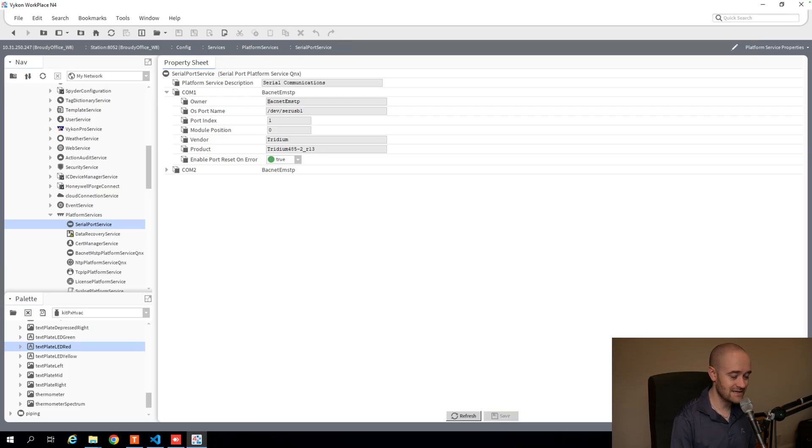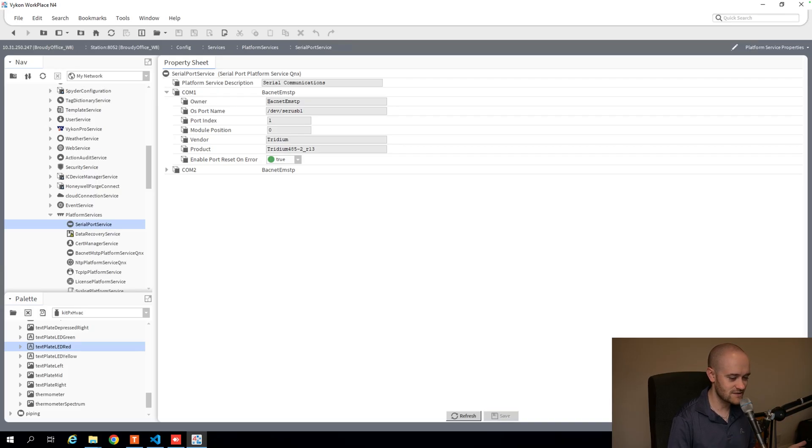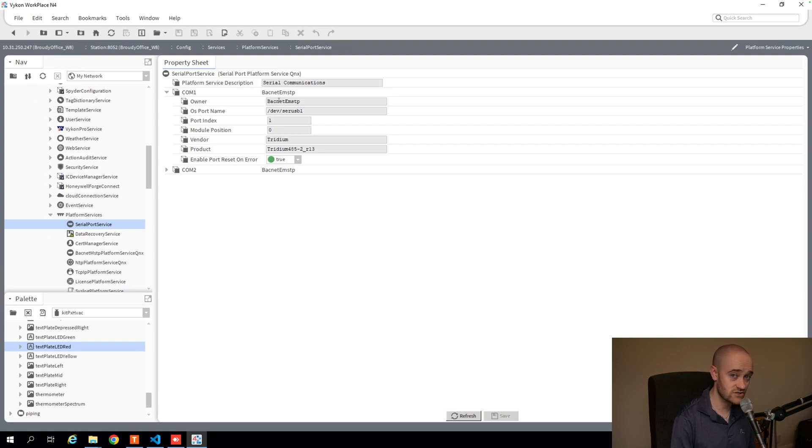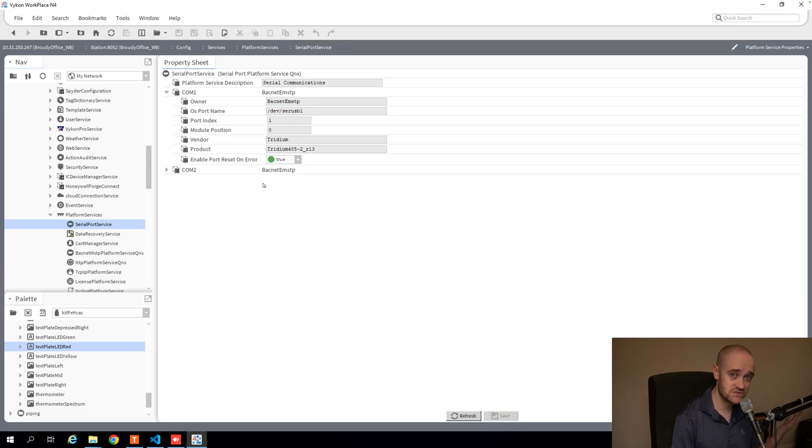And two, whether or not that port is already being used by something else. If you're going onto an existing job and logging into a Jace for the first time and you don't know exactly what's going on or what's where, this is a nice place to start to get an idea of where that COM port is being used, the name of it, and if you have any available ones to use.